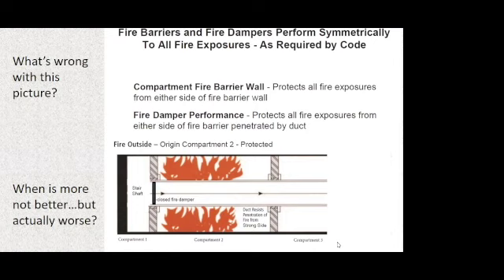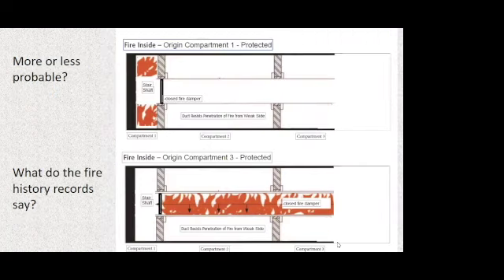And we are very, very commonly making a mistake that renders a whole lot of equipment and ductwork inoperable at exactly the time that it's needed most, because the simplest component of the system did exactly what it was supposed to. Actually, the code instructs us very clearly in section 909 to envision all of the probable fire scenarios. There are a lot of myths out there about which fire scenarios you need to abide by. And I assure you, as someone who has spent a 30-year career immersed in fire science, some people claim they know how the fire is going to attack a building and how it's going to move through the building, and that it'll never do this and it'll never do that. Their crystal ball is better than anyone's I've found yet.